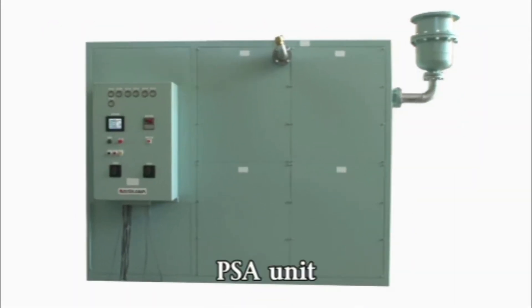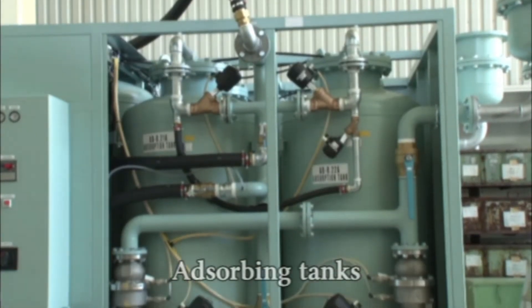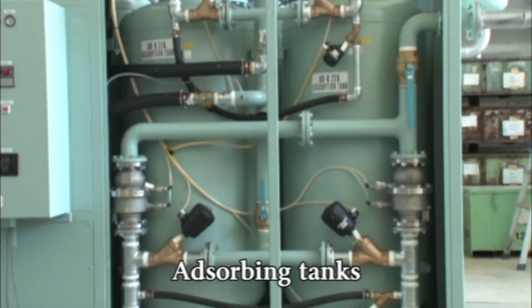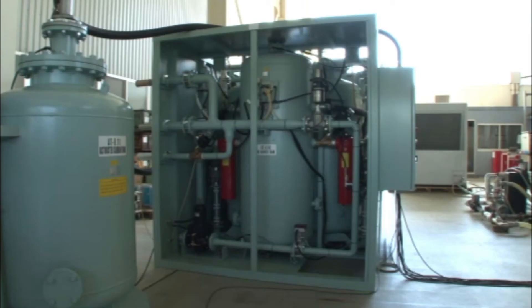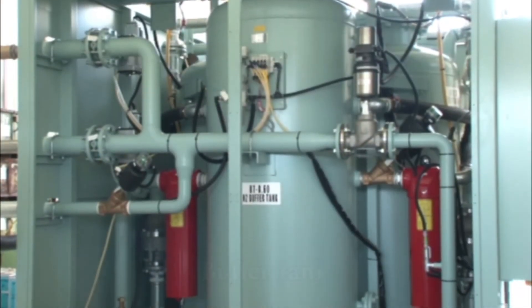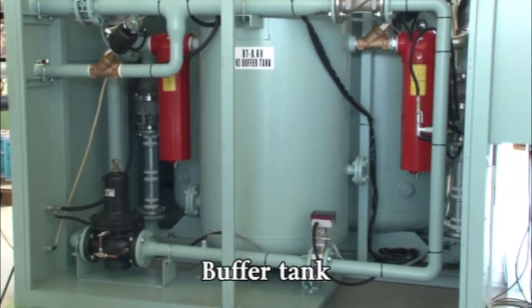The PSA unit consists of two or more pairs of adsorbing tanks and a buffer tank. The dried and cleaned compressed air is fed to the PSA unit, and nitrogen gas is produced by means of removing the oxygen in the adsorbing tanks. The produced nitrogen gas is then accumulated in the buffer tank, so that delivery pressure to the cargo tank can be kept constant.